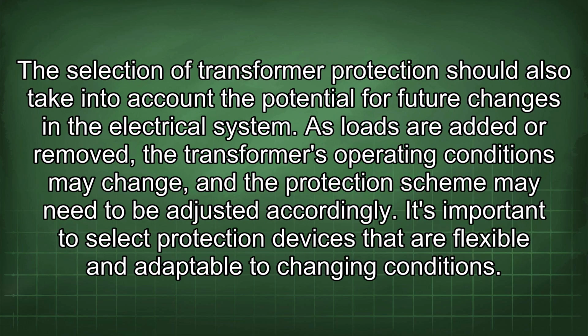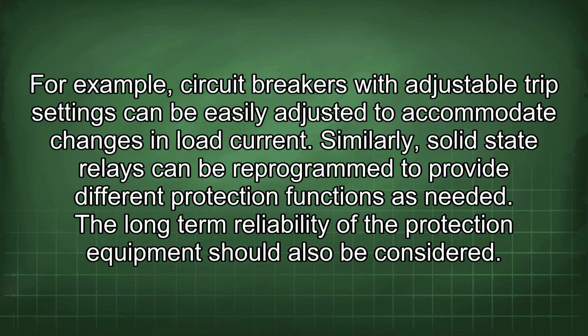The selection of transformer protection should also take into account the potential for future changes in the electrical system. As loads are added or removed, the transformer's operating conditions may change, and the protection scheme may need to be adjusted accordingly. It's important to select protection devices that are flexible and adaptable to changing conditions. For example, circuit breakers with adjustable trip settings can be easily adjusted to accommodate changes in load current. Similarly, solid-state relays can be reprogrammed to provide different protection functions as needed.